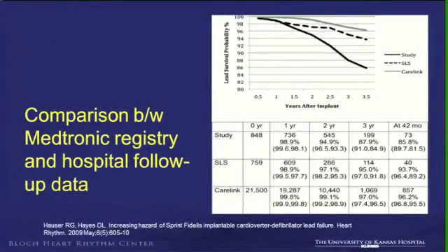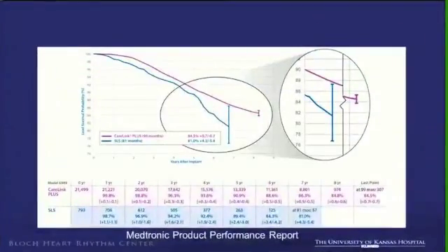And as I mentioned earlier, the comparisons have to be made by real life and product return analysis and actual studies. So if you can see, there's a significant difference in the projected survival of the leads. And this is as of May 2013. So this is the return lead analysis and the CareLink data. It's not increasing, but there is a kind of plateaued effect or the same rate of failure of the Sprint Fidelis leads.